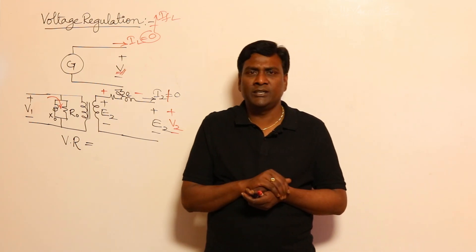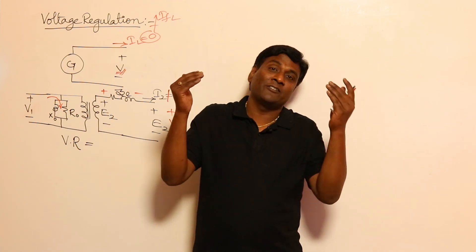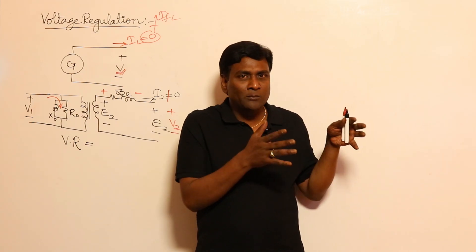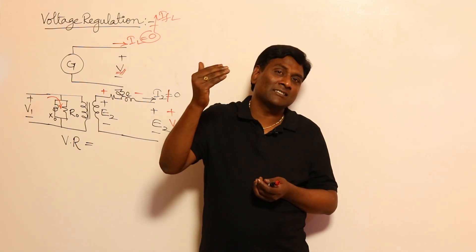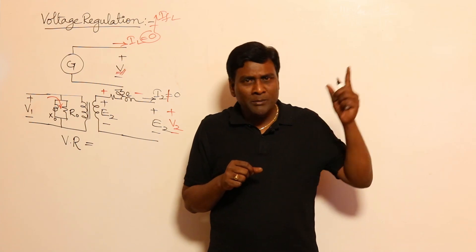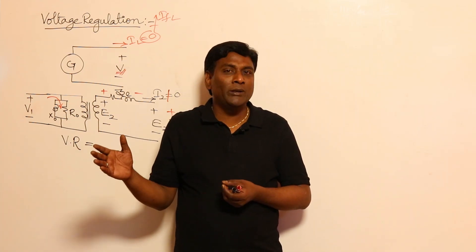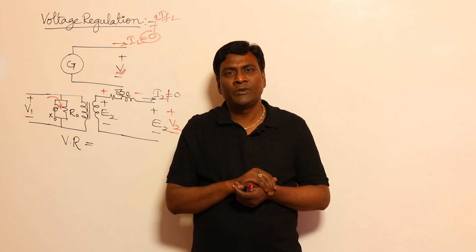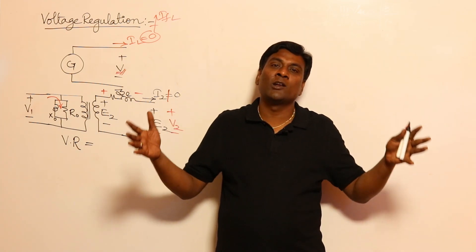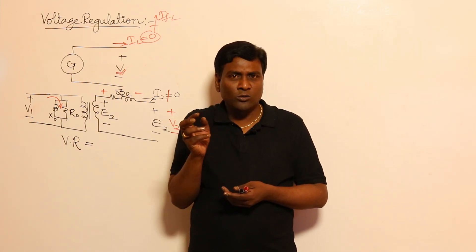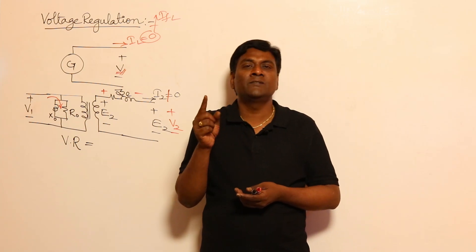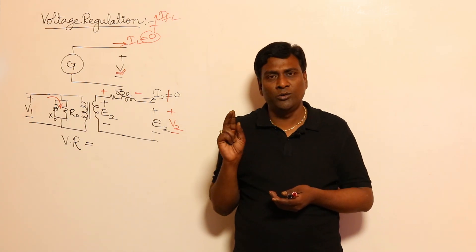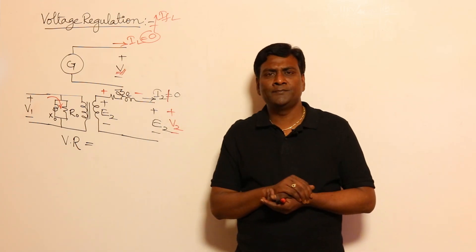Let me add the alternator here. Once an alternator is connected to the infinite bus — the national grid — for example, a power generating station in Hyderabad connected to the national grid: even if Telangana doesn't need power, Haryana or Tamil Nadu might. Once connected to the national grid, the alternator always operates at full load, because its catchment area is all over India. So: distribution transformer — high load variations; power transformer and alternator — almost always full load.